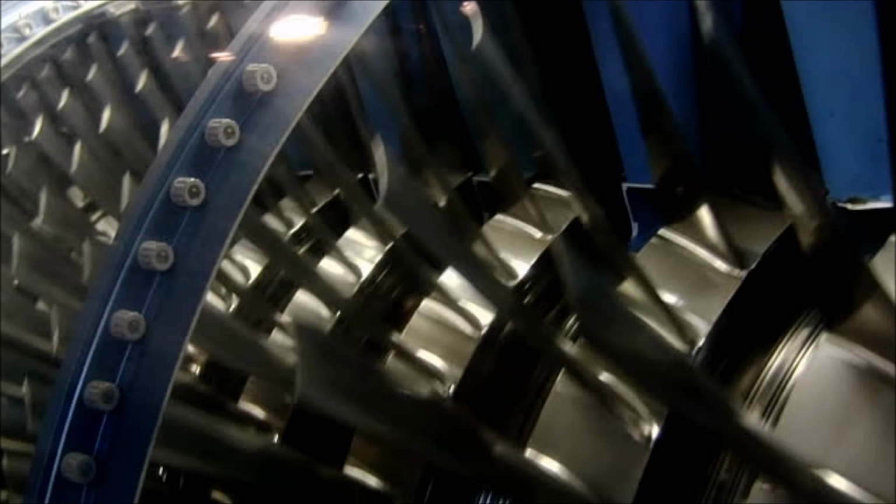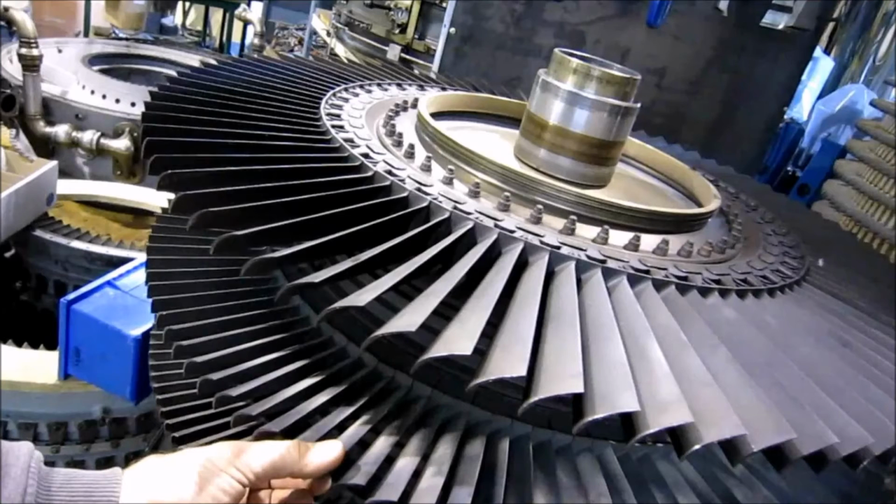Radial flow type, or 2. Axial flow type. Centrifugal compressors, also known as turbo compressors, are radial flow type, rotodynamic compressors. These compressors are widely used in large capacity refrigeration and air conditioning systems. Axial flow compressors are normally used in gas liquefaction applications.